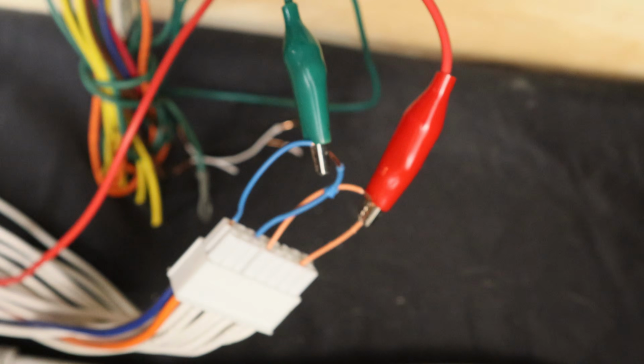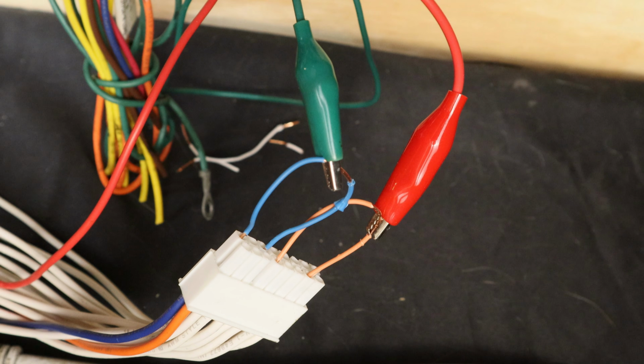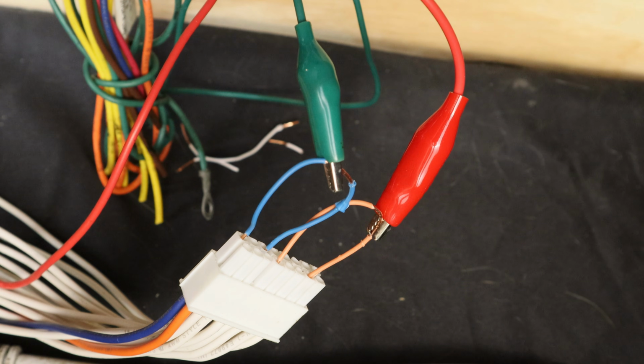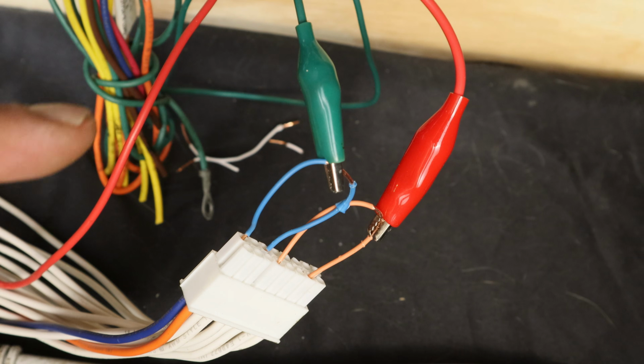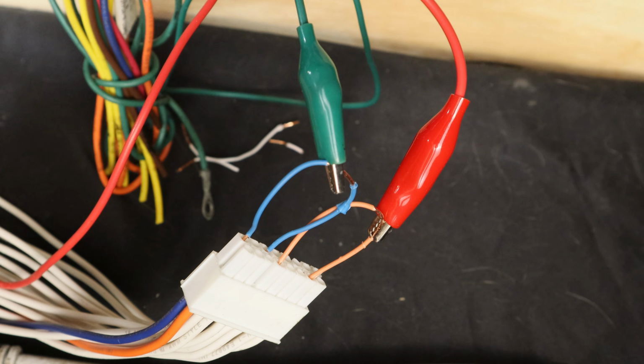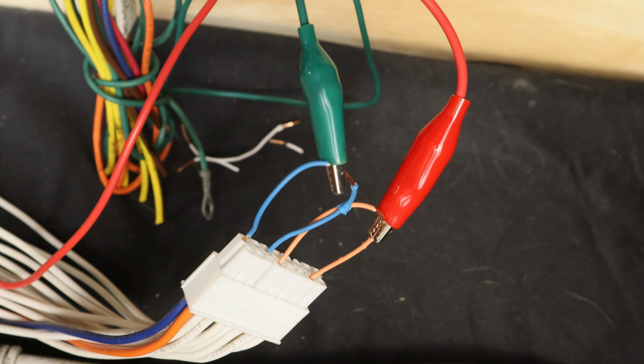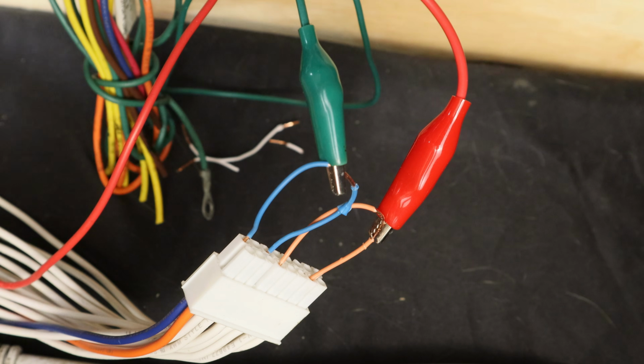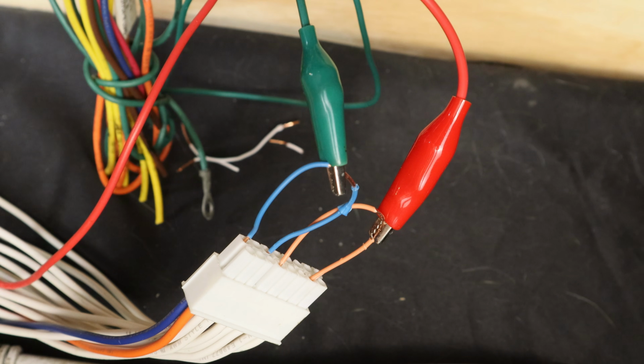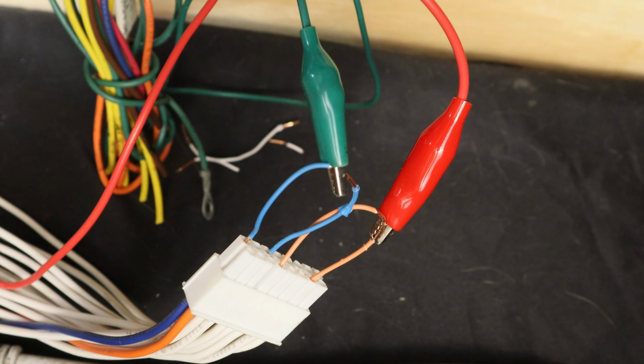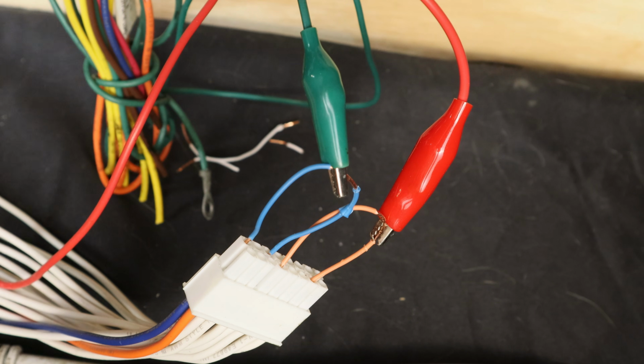Now, I did mention earlier all these signals along this wire, they're all DC signals, but we can use a 24 volt signal just to wake the motor up. We're not going to have any control over it. So if the motor does start, it's going to default to whatever programming logic is in there. So it can start up at idle speed as if you're just running the fan, or it could run full speed like second stage cooling.